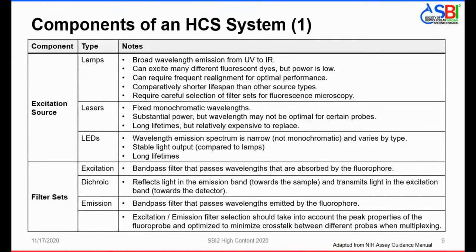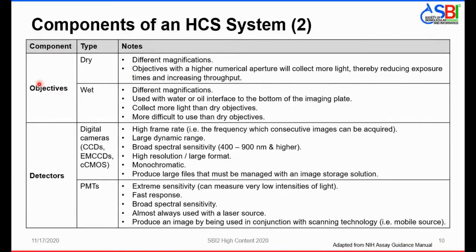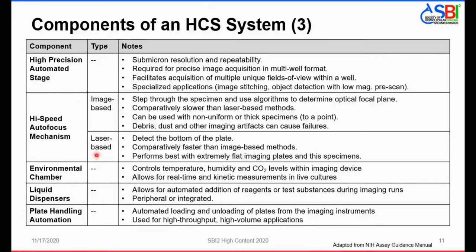The HCS system is composed of an excitation source such as a lamp, laser, or LED; a set of excitation-emission filter sets; a variety of objectives for low and high magnification; imaging detectors such as digital cameras; a high-precision automated stage to facilitate movement of the sample and accurate imaging of individual fields of view; and high-speed autofocus mechanisms. Optional components of HCS systems include environmental chambers, liquid dispensers, and plate handling automation.